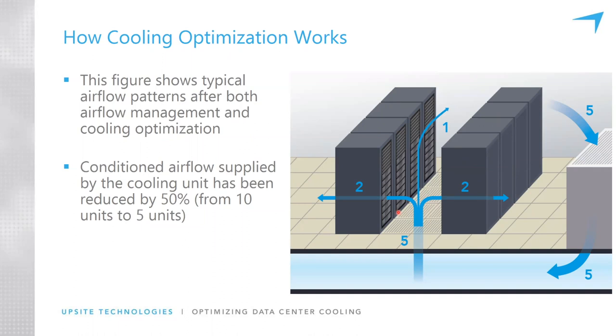Just before we go on to that, I want to say that the amount we can reduce the fan speed depends on how much airflow management has been implemented in the room. We couldn't do this if there were missing blanking panels in these cabinets. We couldn't reduce the fan speed by half and very closely match the flow rate through the cooling units to the demand flow rate of the IT equipment if there were supply tiles in the wrong locations, if there was air flowing underneath cabinets, or if there was hot air flowing around the ends of the rows. So the more containment we put in place, the more we can optimize and closely match the flow rate moving through the cooling units to the flow rate moving through the IT equipment.